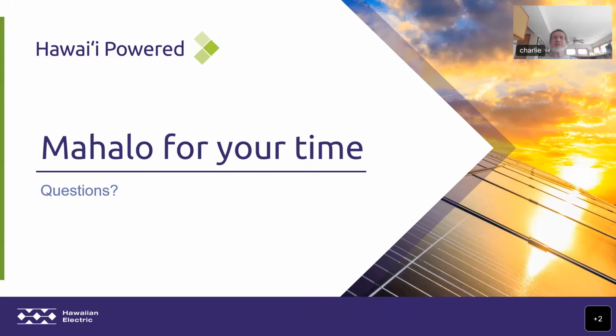Here's one. I don't know if you'll have heard about this or not, but we'll ask. Have you ever used or heard of substations that apply secondary bus differential relays? Is that protection scheme worthwhile? Yes, we do have some of those in place at our critical substations. So dual differential, current differential bus protection. Again, you just have to make sure that the circuit breakers have adequate CTs on them, and yeah, you can make that work. And we do have that again for our critical stations.